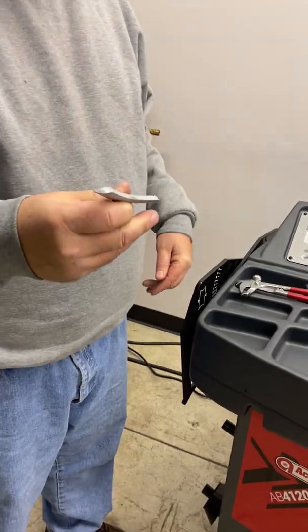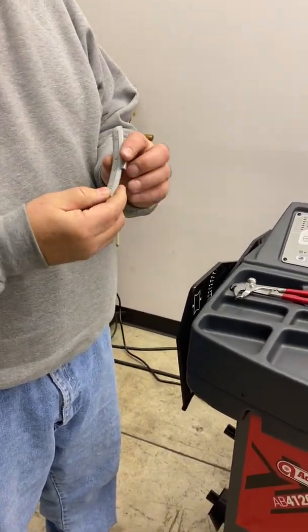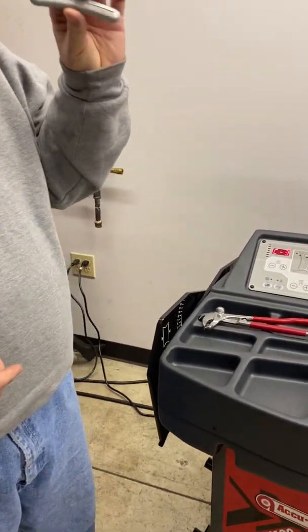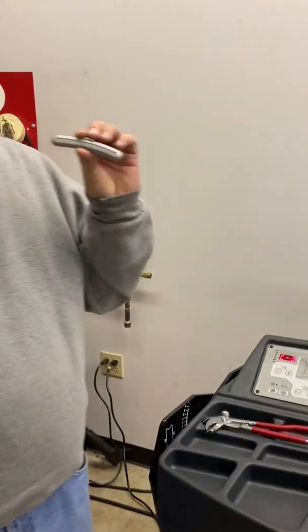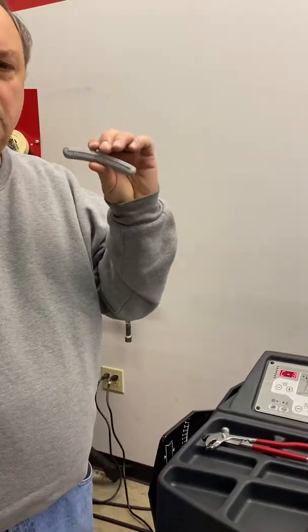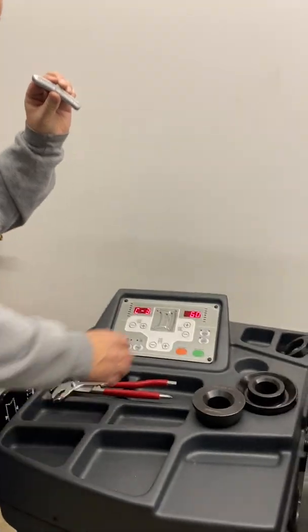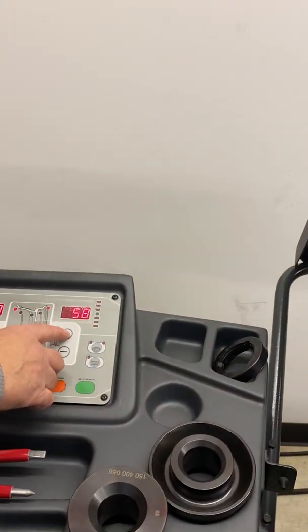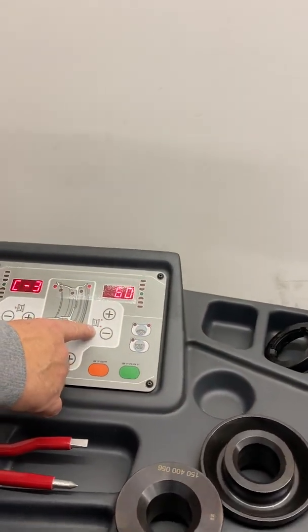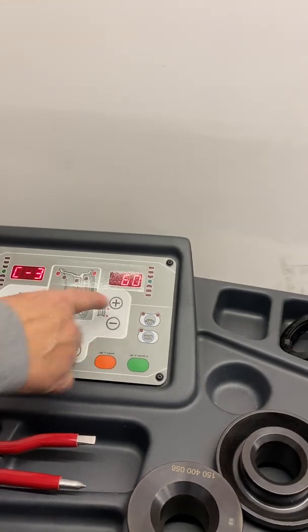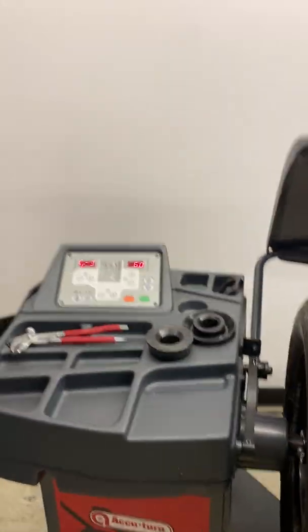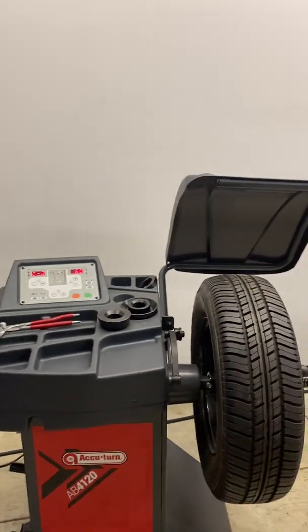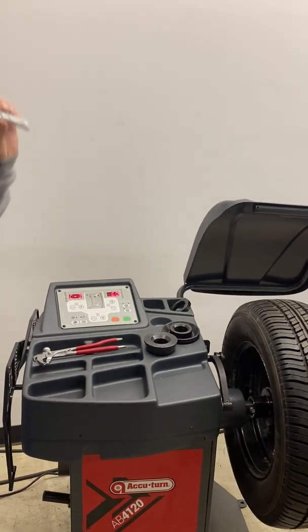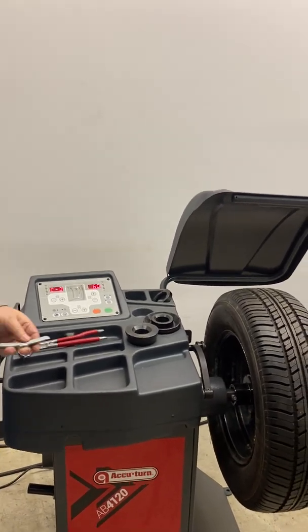to use. The standard calibration weight that comes with the machine is 60 grams. However, if the weight you have is not the calibration weight and you choose to use a different weight, you can now use the plus or minus button on the diameter to change the gram weight of the weight that you will use for calibration. Make sure this is correct. We are using a 60 gram weight.